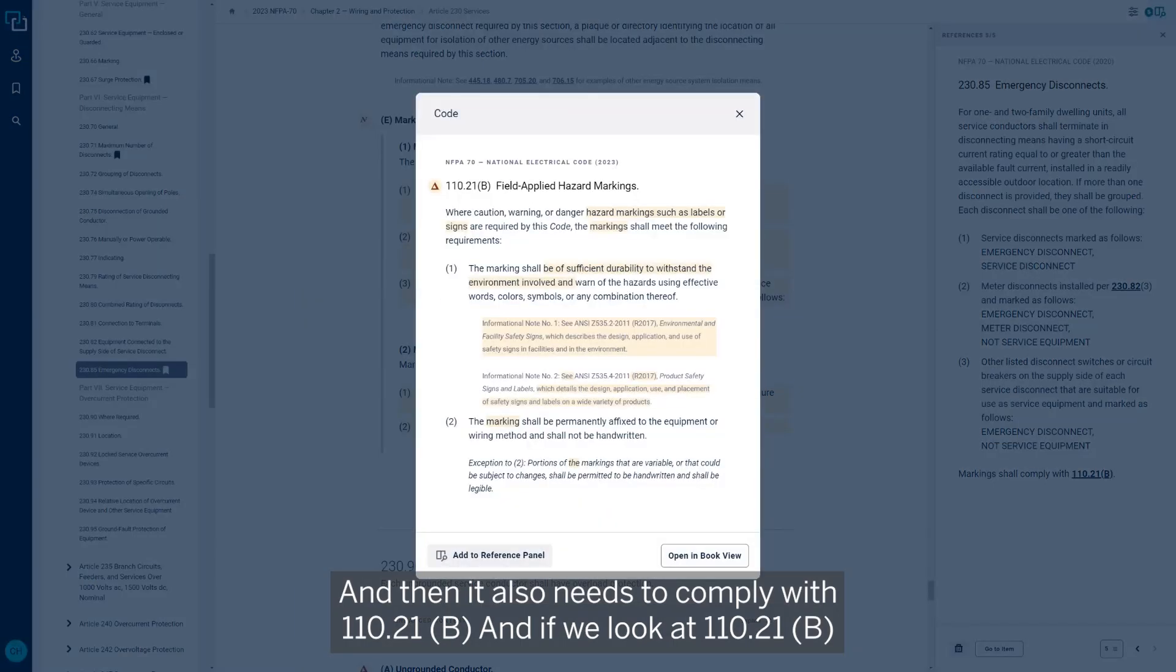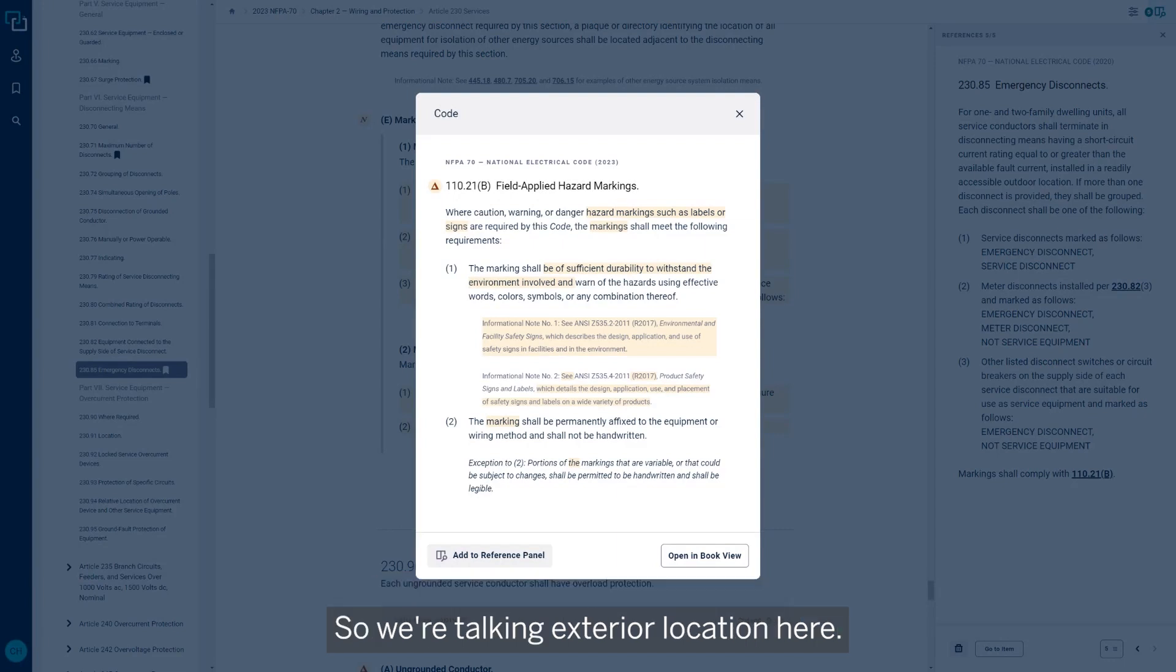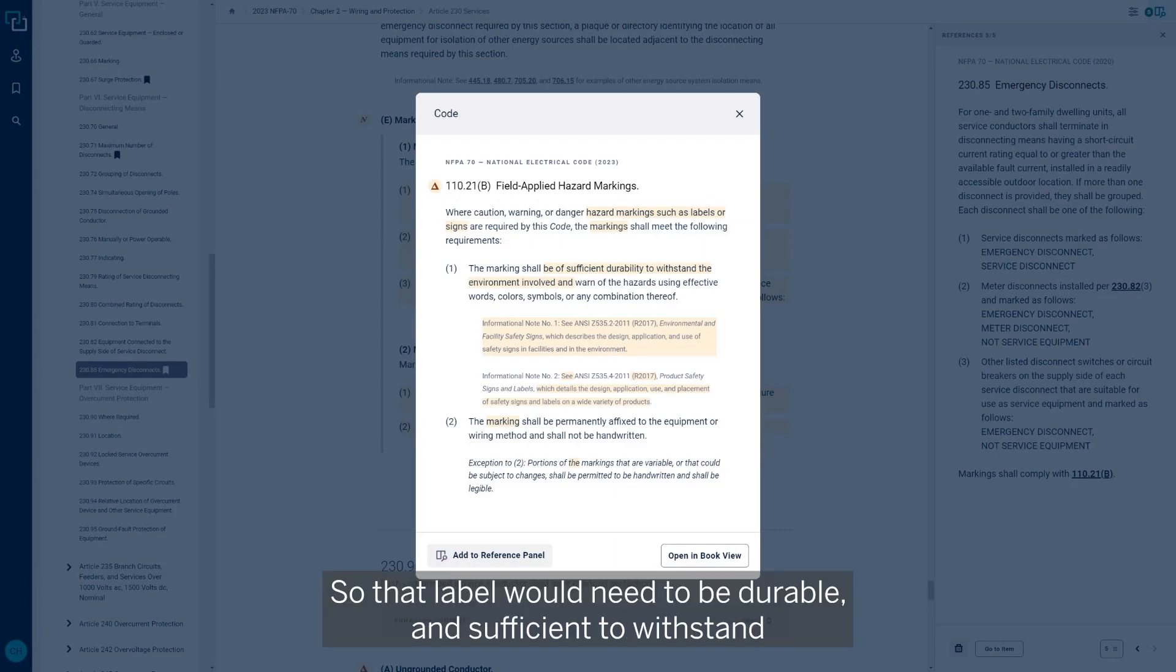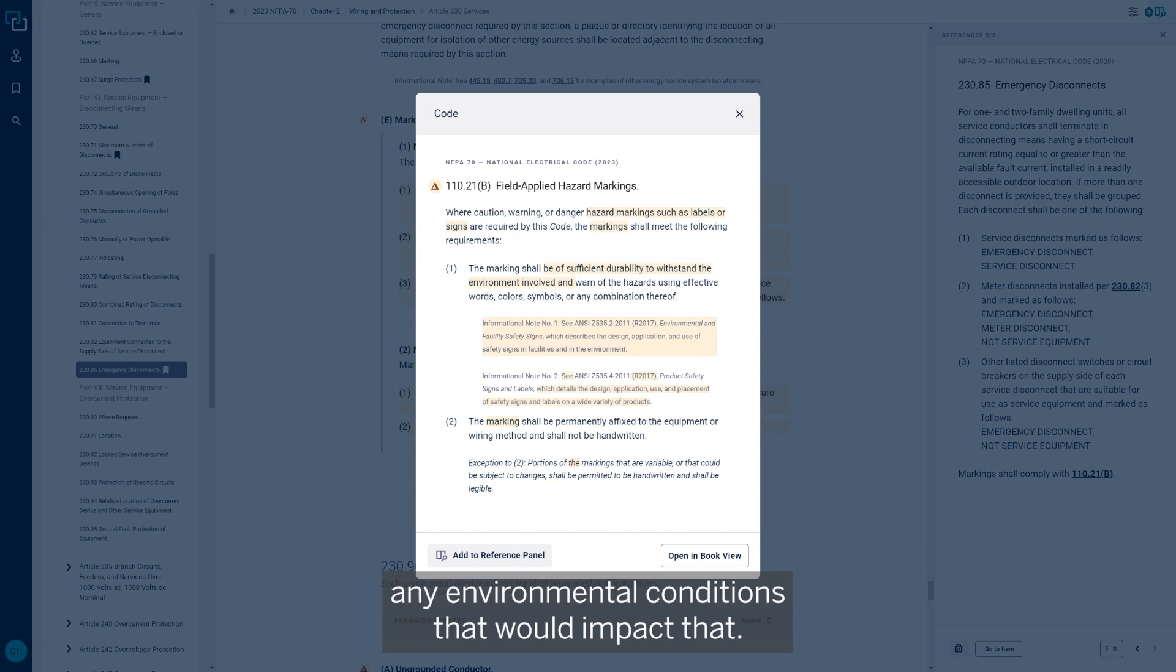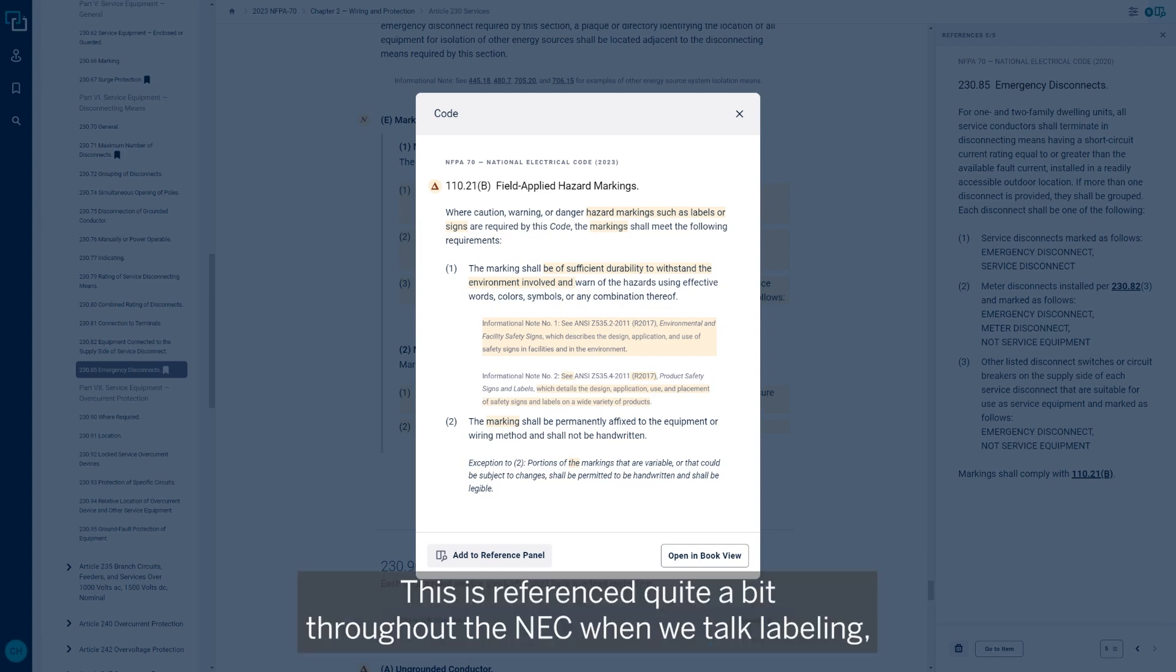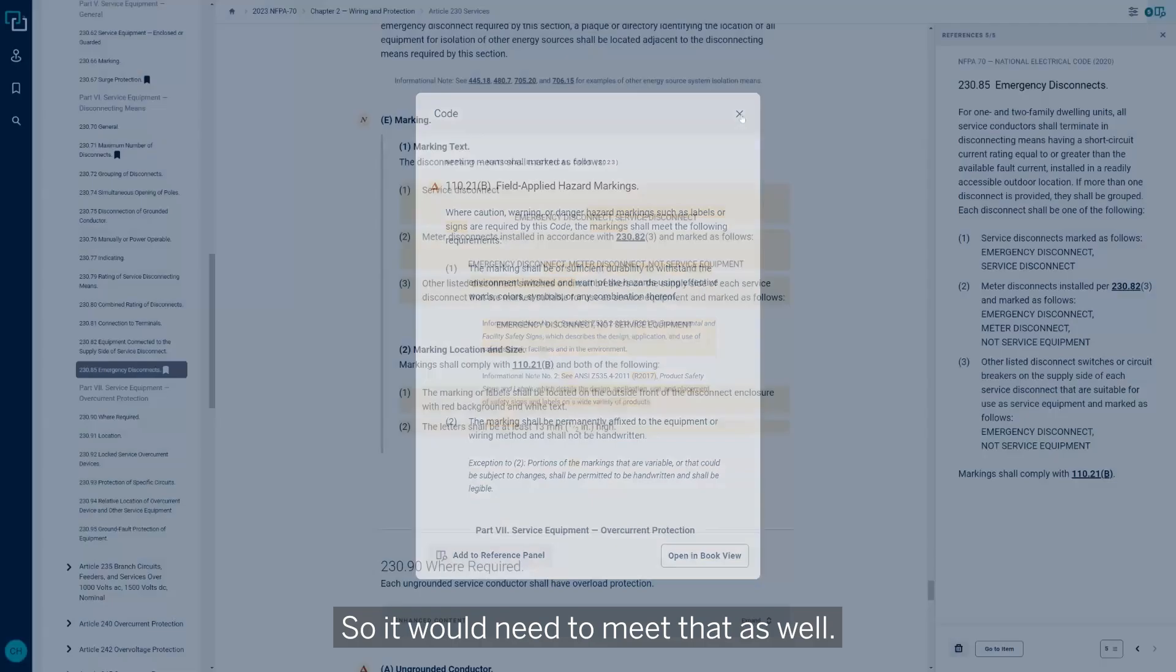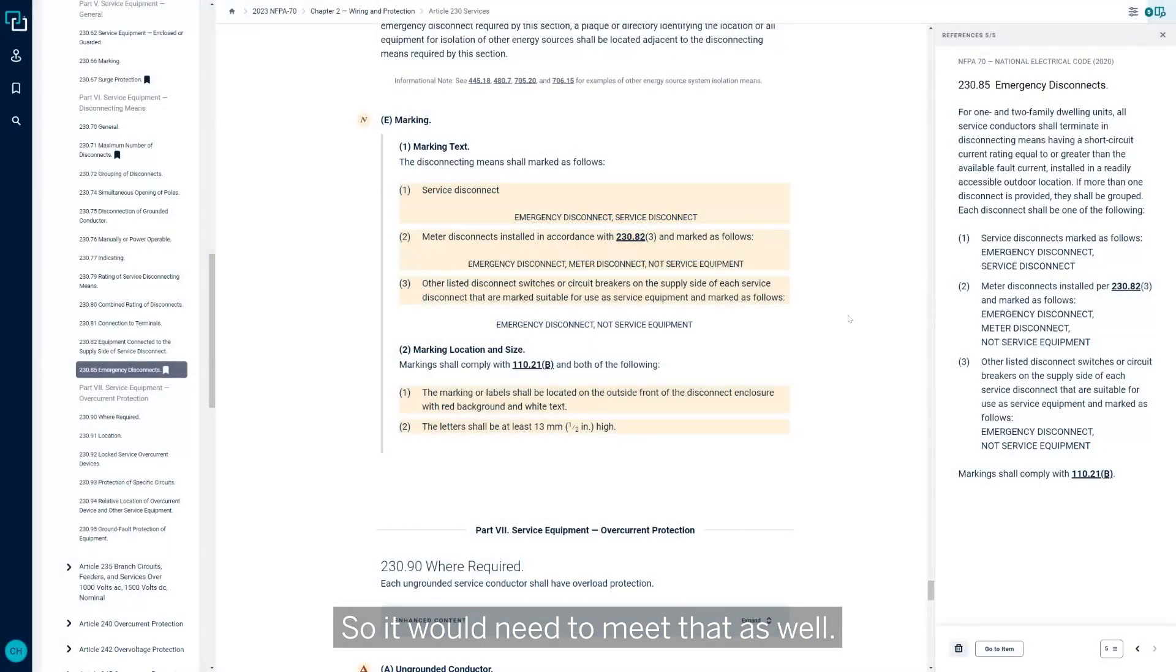And then it also needs to comply with 110-21-B. And if we look at 110-21-B, that has to deal with the durability of that label. We're talking exterior location here, so that label would need to be durable and sufficient to withstand any environmental conditions that would impact that. This is referenced quite a bit throughout the NEC when we talk labeling, making sure that those labels are going to be withstanding that environment that they're installed in.